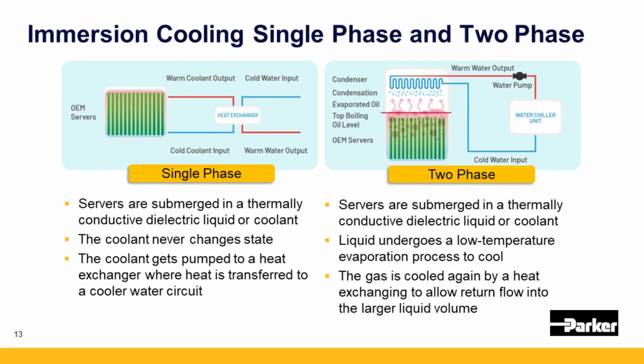So again, single phase and two phase - single phase, shown top left, is essentially circulating fluid through the tank and rejecting it to outside heat. Two phase is similar, but you're boiling this fluid directly off the IT gear. It becomes a gas that you have to capture, then condense back down, either inside the tank or outside. You capture that and pump it back in, but the key is being able to manage and deal with that process.